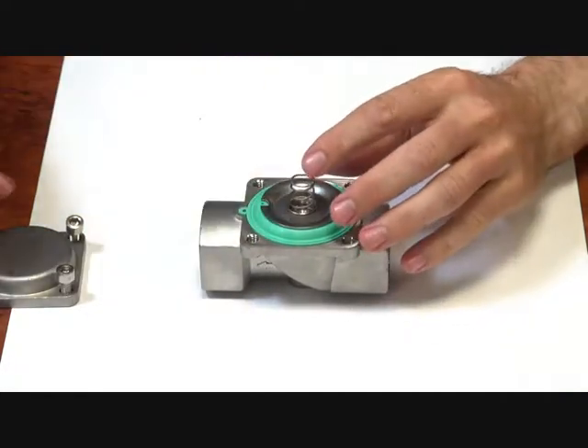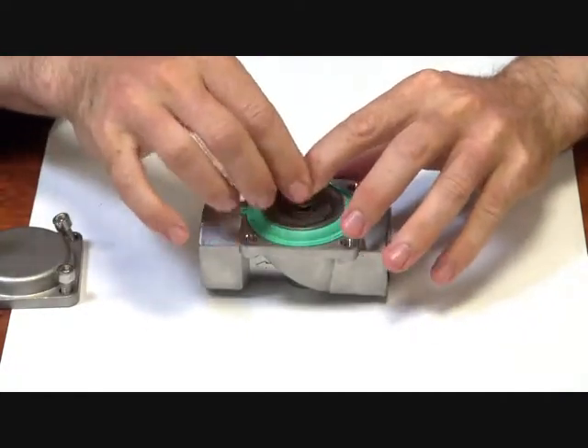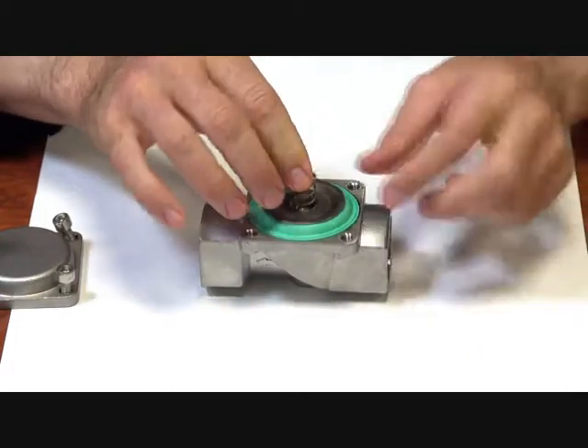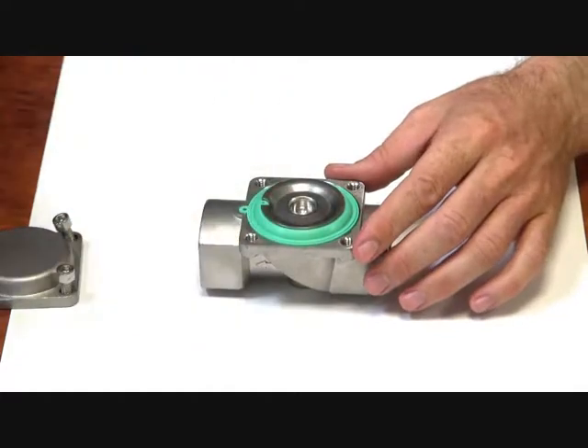So you can see it needs a differential pressure because this spring is actually holding the diaphragm in place. Now the 0.3 of a bar in this case is actually to overcome the spring tension, and push this up.